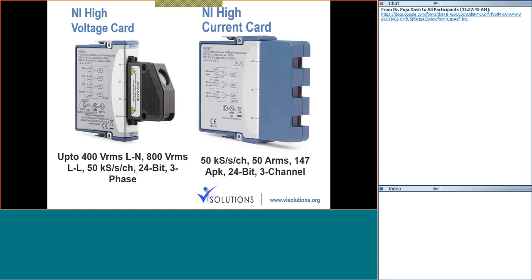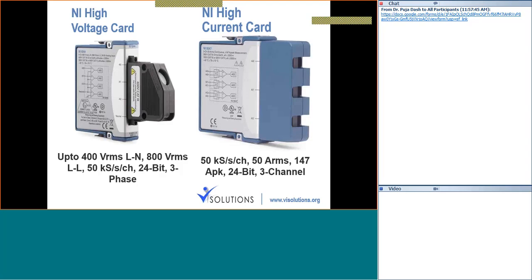So when you get the data, you just get the waveform data. If you apply some sort of logic there, you can convert the waveform information to an RMS value. It's basically a root mean square application. And you have 3 channels, which means if you have a 3-phase measurement, you can potentially make use of this. So you have a specific set of hardware which is going to help you get data from the grid.